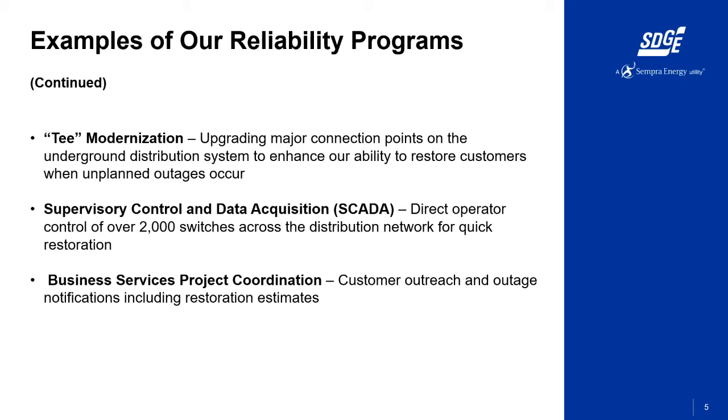After Tee modernization, we have the SCADA program. SCADA is short for Supervisory Control and Data Acquisition, SCADA. And SCADA provides direct operator control of over 2,000 switches across the distribution network from the Mexican border to the Laguna Niguel part of our Orange County district, 2,000 switches, and the operators can open or close these switches on a moment's notice electronically. They will also have access to real-time data in terms of information like load and voltage and so forth, and any kind of fault targeting information that comes back almost immediately through the SCADA system. It's a system that we use quite extensively.